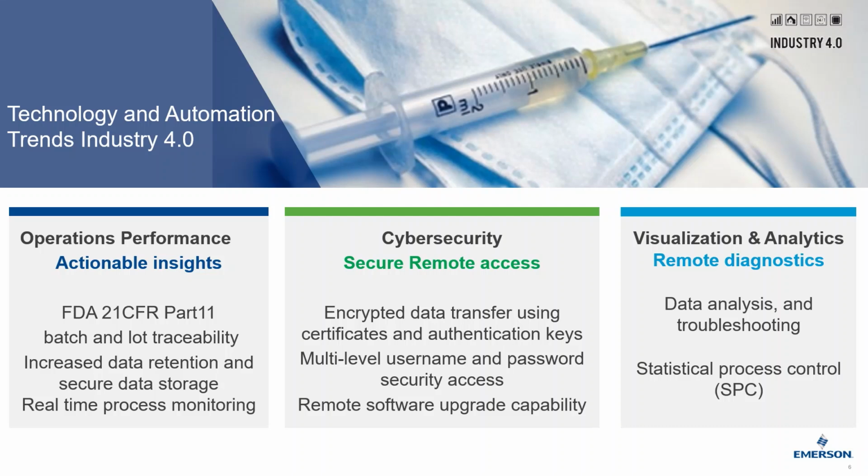Our survey of device manufacturers revealed the most top-of-mind concerns were actionable data, data that's secure, is regulatory compliant, and that allows deeper analytics using SPC quality visualization tools for batch and lot control. Regulatory compliant process control data usually requires an uneditable audit trail recording all monitored process parameters, whether this is in hand-printed or in electronic format.